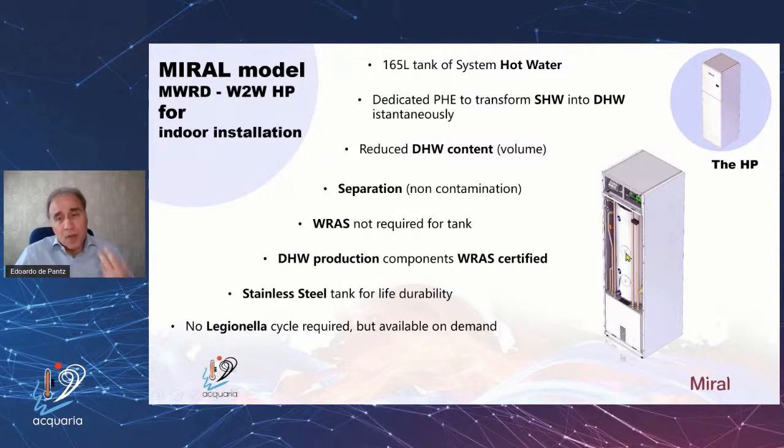So the domestic hot water is being produced by a heat exchanger external to the tank, but inside the unit, obviously, so that the domestic hot water is produced instantaneously when there is a request. Given this, the tank doesn't need to be WRAS certified because it contains only technical water. For this reason, there is no need for a Legionella cycle. This also guarantees that the domestic water amount is reduced to a minimum, and there is no contamination between technical and domestic water. The tank is standing still in any case.